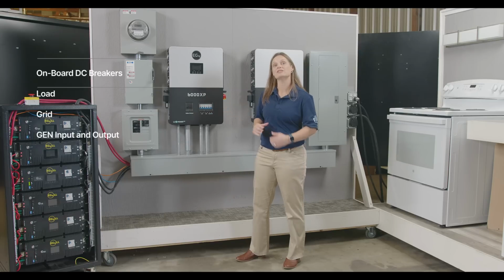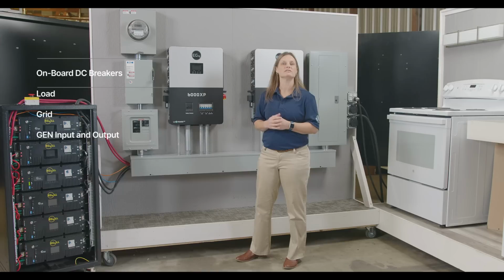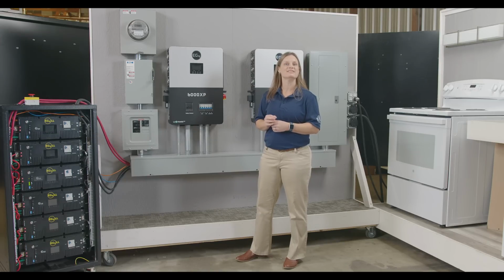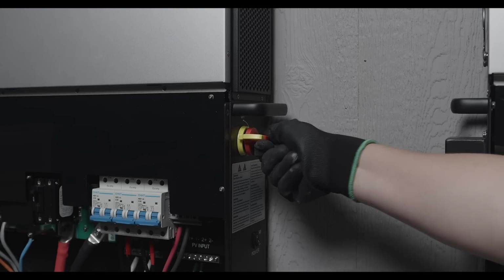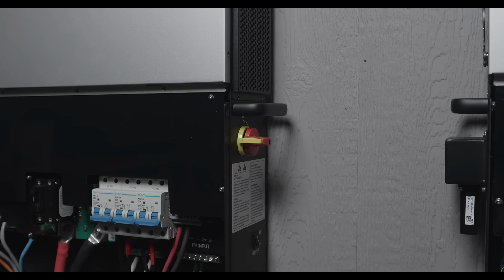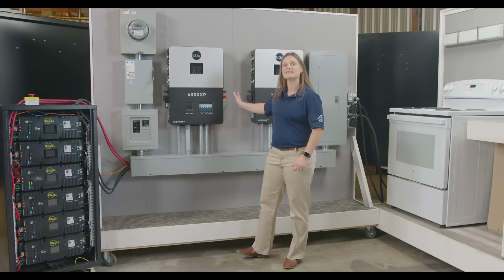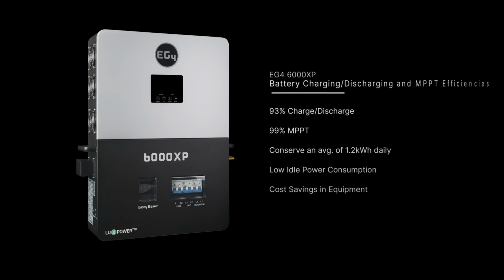It also offers GFCI and even arc fault detection on the MPPT, setting it apart from others on the market. And guess what? Like the 18K, it even has a disconnect switch for the PV input. This system is designed to be user-friendly and cost-effective. Even though this inverter is capable of handling lots of power, its idle power consumption is the lowest available. Idle consumption is about 50 watts with battery, less than 30 watts with PV, and less than 50 watts with AC.